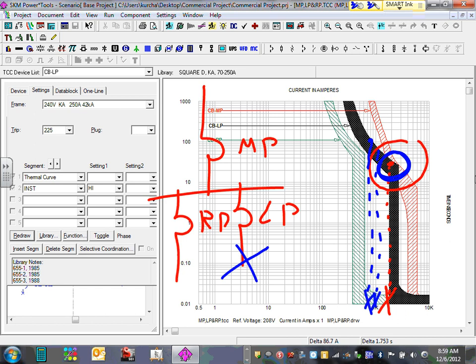I have a good example. I was at a Cup Foods putting in a timer switch, and I pulled the switch out of the wall, and the hot wire hit the frame of the switch, and it blew the main and took the whole place down. That's a bad day. That's bad coordination. That's a very bad coordination.